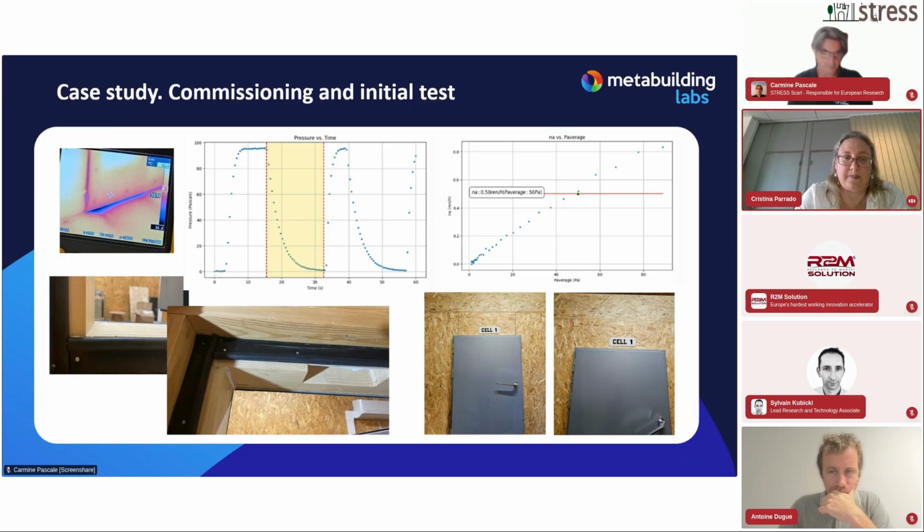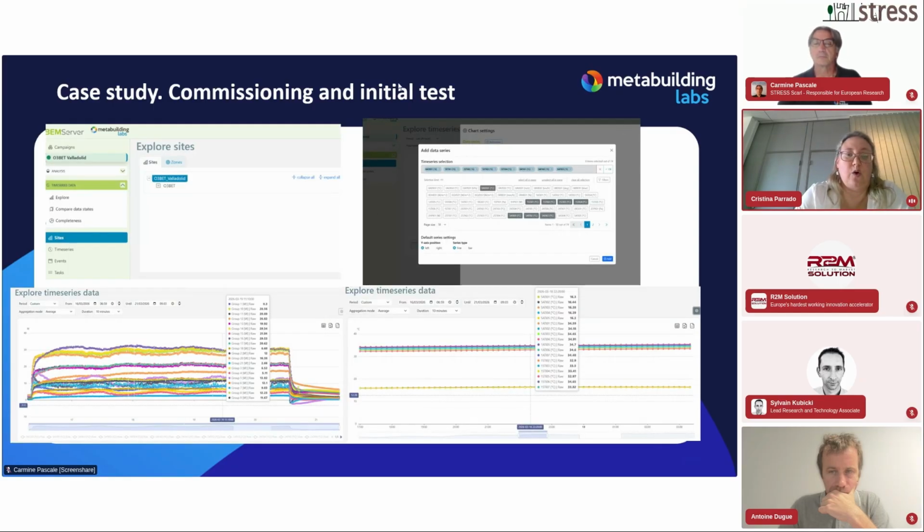So next one, please. With this calibration wall, we start to use different powers. The best one that we have reached in our test is 400 watts. And we have done tests also with a different sequence of heatings. And as you can see, we have a very good homogeneity in the temperature, and also we have a lot of data to know the heat loss all around our cell. So we have characterized our cell properly. And now, next one, please.